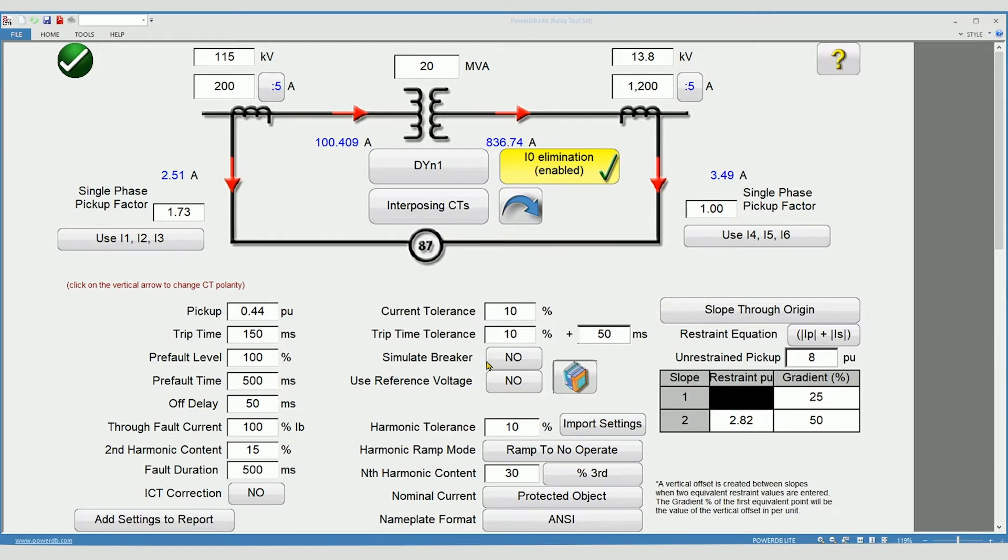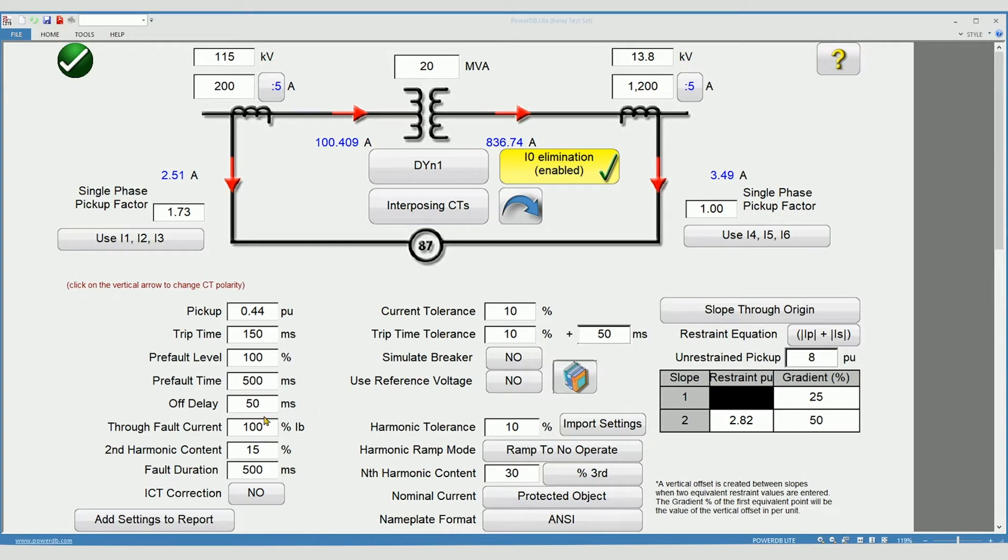Simulate breaker tells the test plan to leave the current on after the trip is received long enough to simulate the opening time of a breaker. Off delay defines the amount of time applied for simulate breaker.